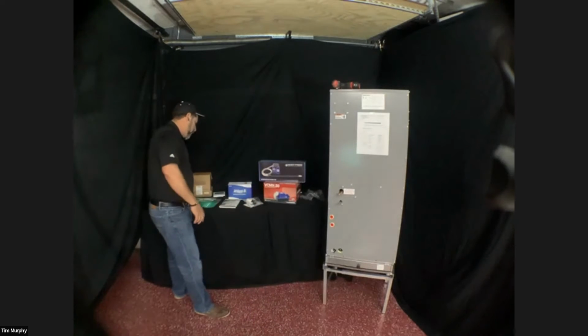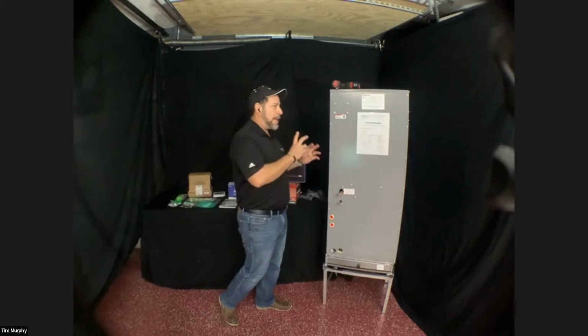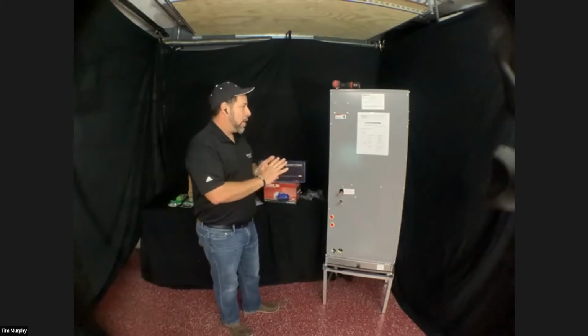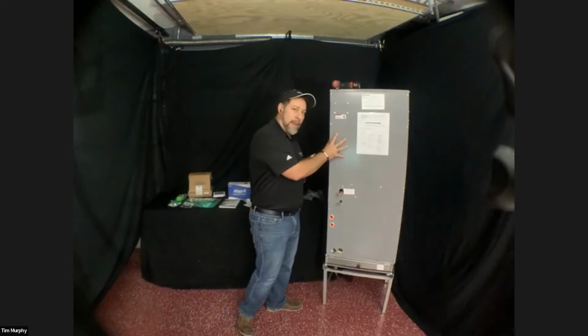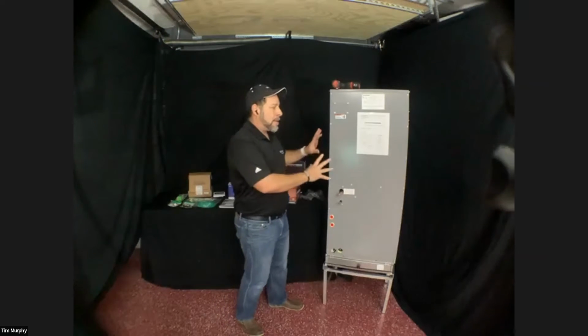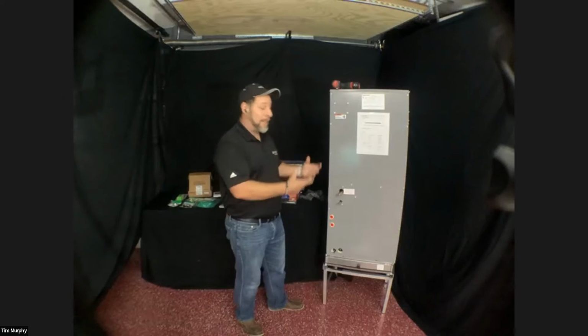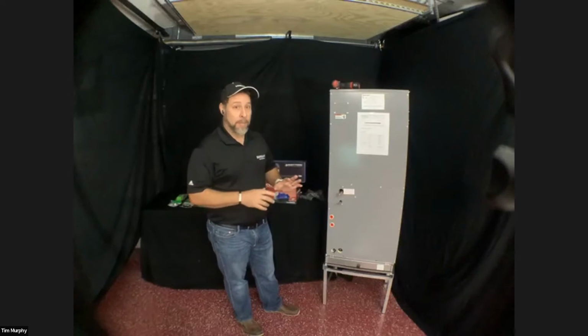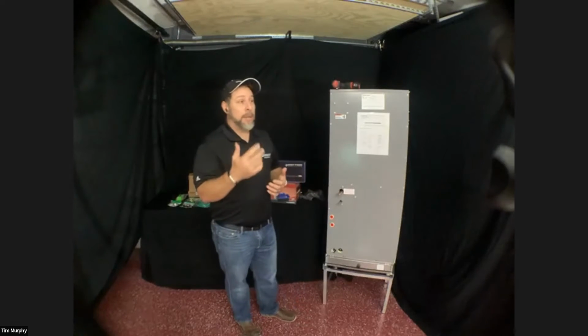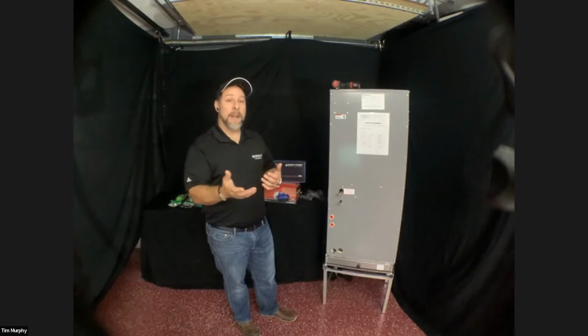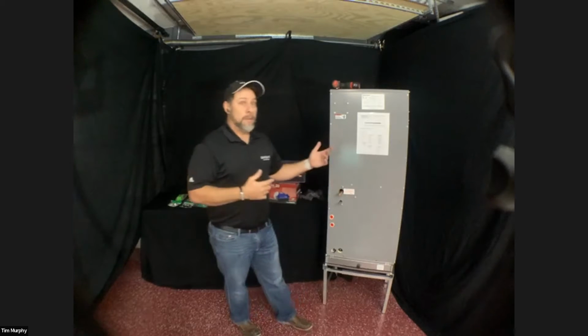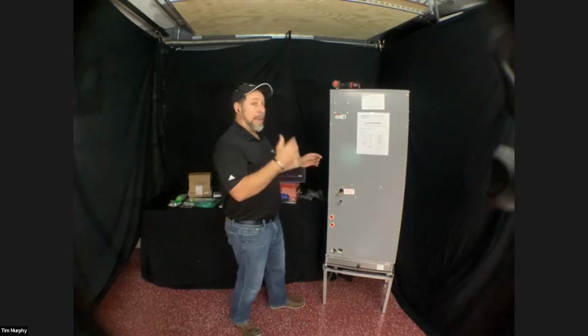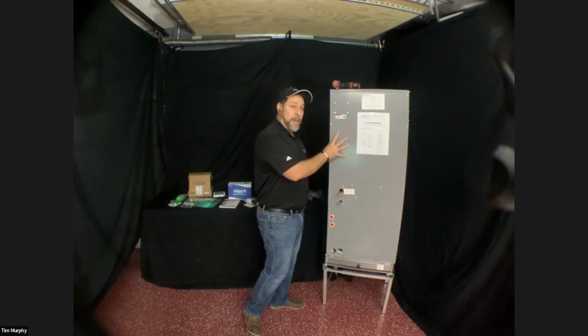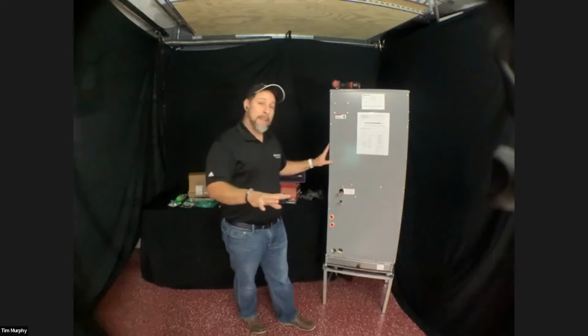Another thing I do want to mention, we're going to go over some installation nuances, right? As I mentioned before, this looks like a regular air handler, but it still needs to be thought of, when it comes to installation, as a regular high wall mini split. Why is that important? Maybe just ask you guys, where is the expansion valve located on a typical mini split system? Typically it's outside, right? Just like with those, this also, the expansion valve is located outside. And why is that important?